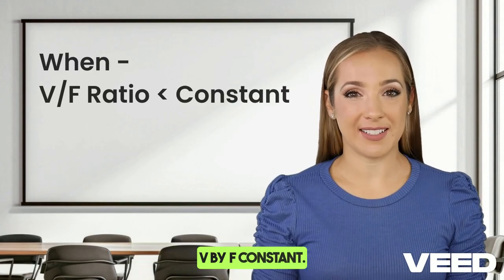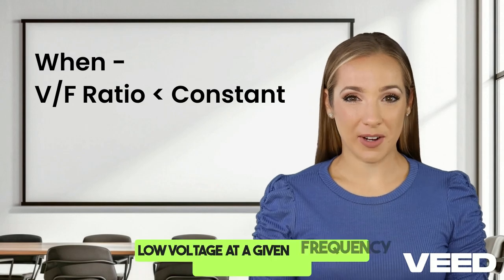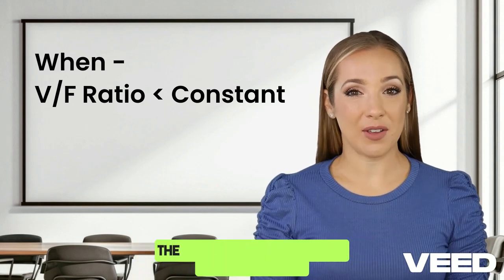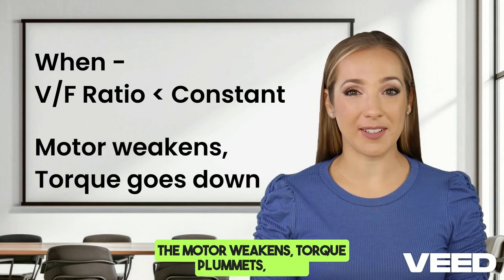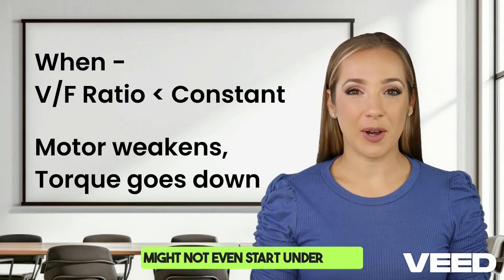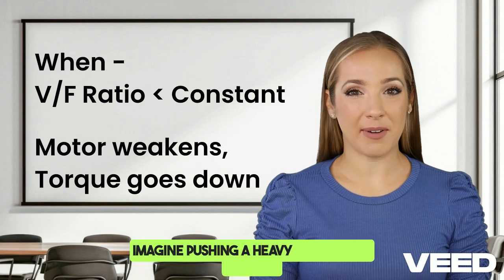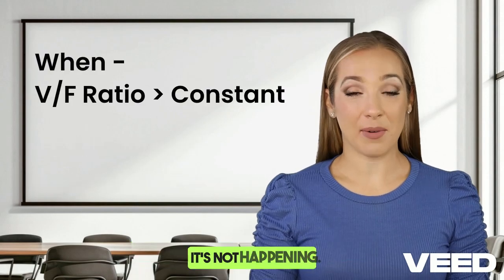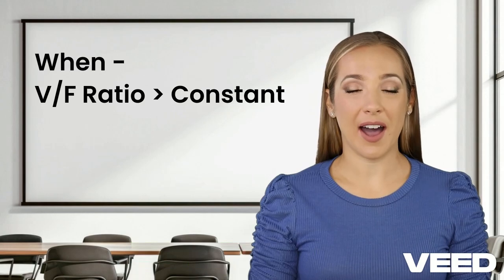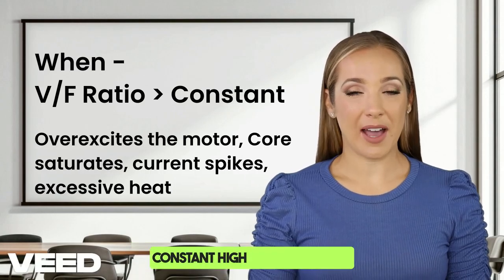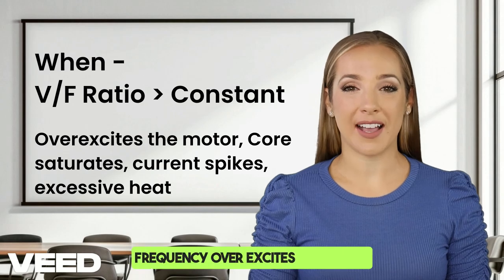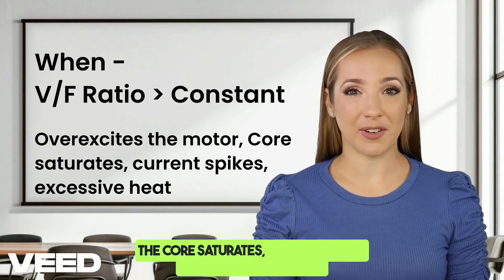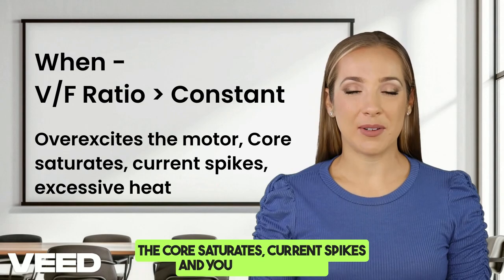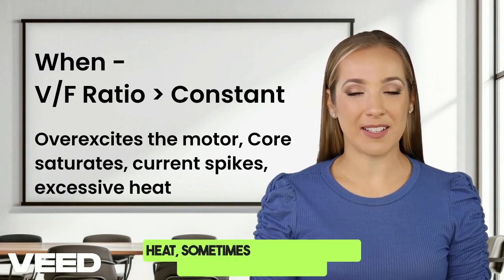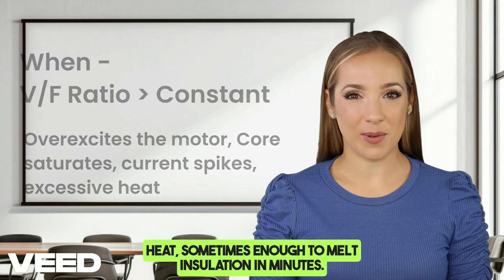V by F, constant, low voltage at a given frequency starves the flux. The motor weakens, torque plummets, and it might not even start under load. Imagine pushing a heavy cart with a feather. It's not happening. V by F, constant, high voltage at low frequency overexcites the motor. The core saturates, current spikes, and you get excessive heat, sometimes enough to melt insulation in minutes.